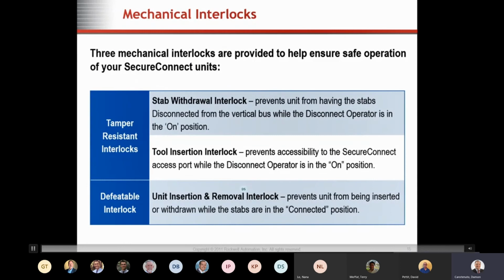Okay, some of the interlocks that they were talking about: you have the stab withdrawal interlock. It stops the stabs from being disconnected while the operator is on. And of course, along with that, you have the SecureConnect access port that cannot be accessed while the power is on as well. One item that is defeatable is the insertion and removal interlock, which helps prevent the insertion tool from being used while the stabs are in the connected position, but that is defeatable in case there would be a problem. You still can get your unit removed or installed.